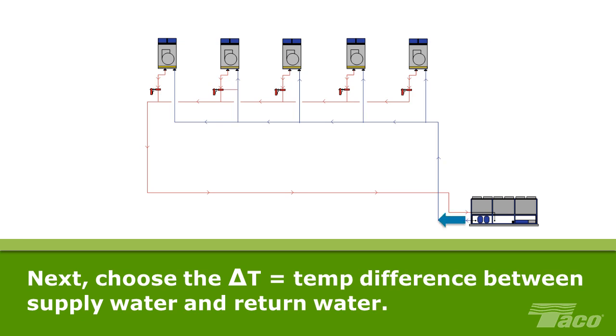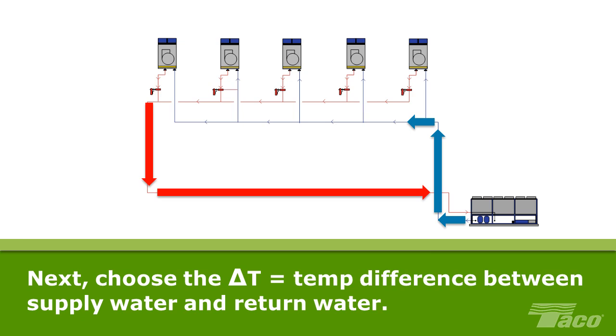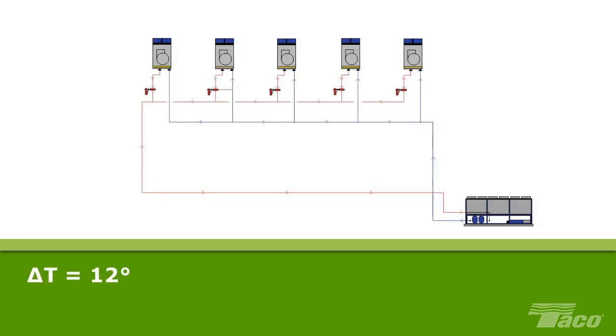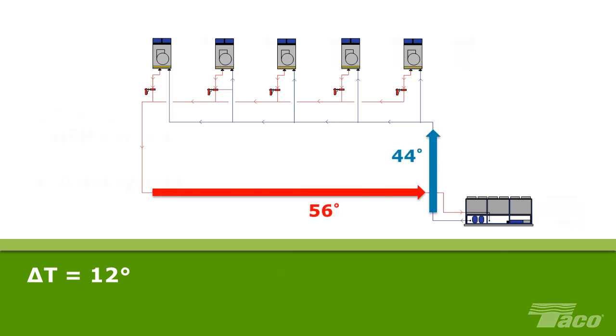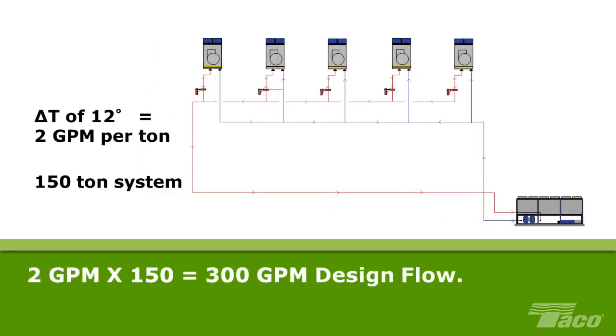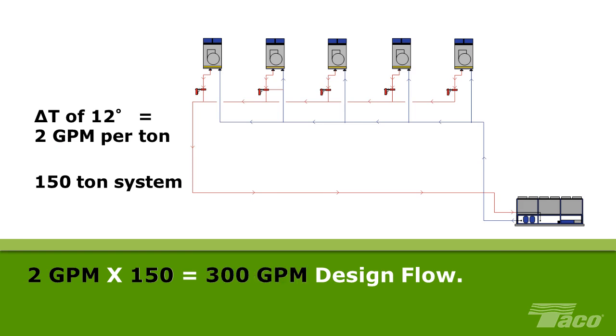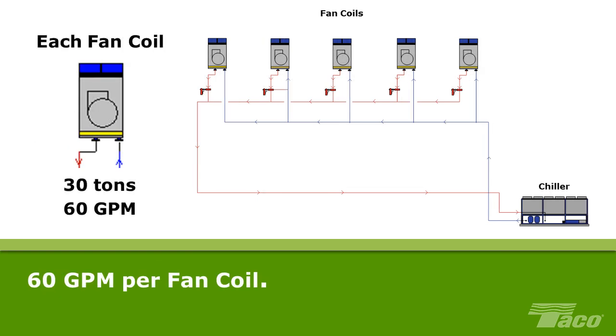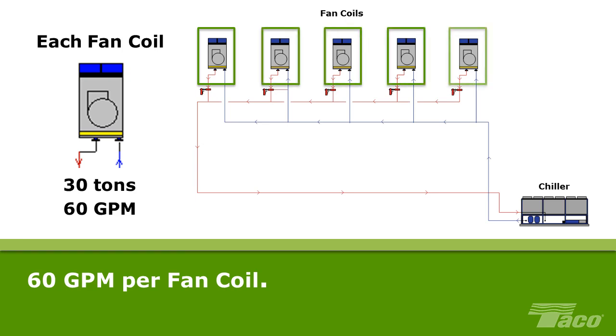The system designer then chooses the delta T for the system. This is the temperature difference between the system fluid leaving the chiller and the return fluid. In this case, we'll say delta T is 12 degrees. The water leaves the chiller at 44 degrees and returns at 56 degrees. Basic hydronic system calculations tell the designer that a delta T of 12 degrees equates to 2 gallons per minute per ton, which makes the design flow of the system 300 GPM. The fan coils are all of equal size, 30 tons, and each requires 60 gallons per minute of flow.